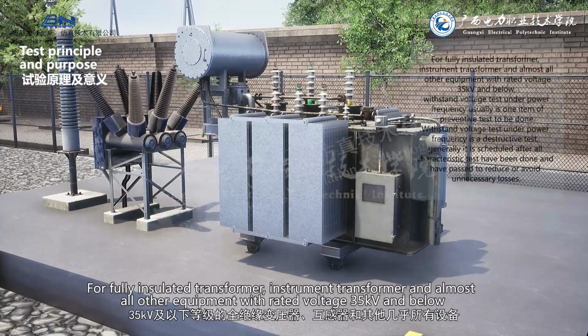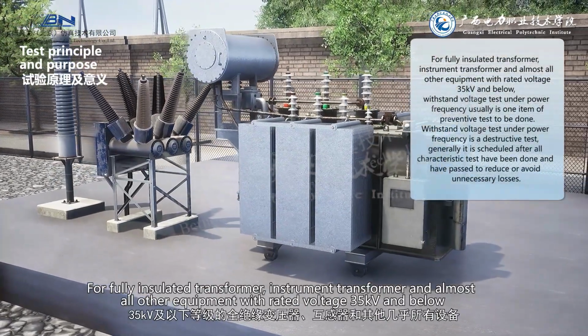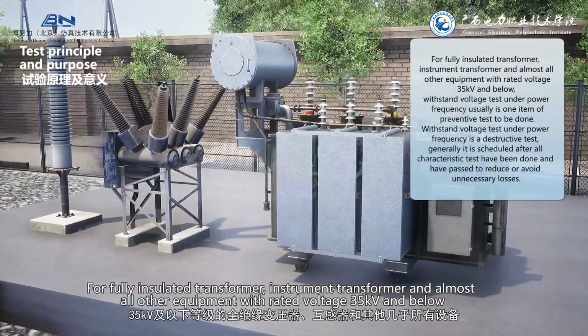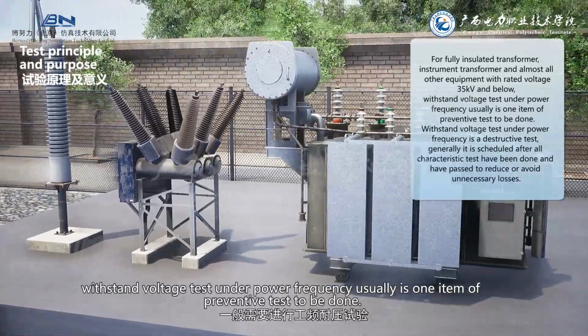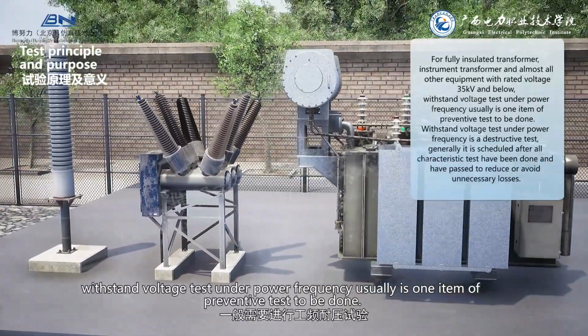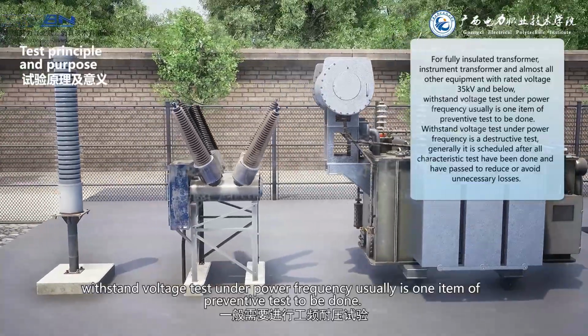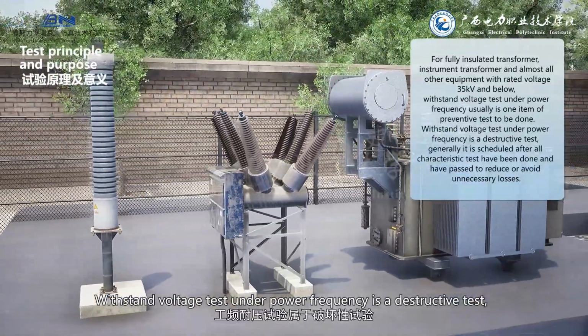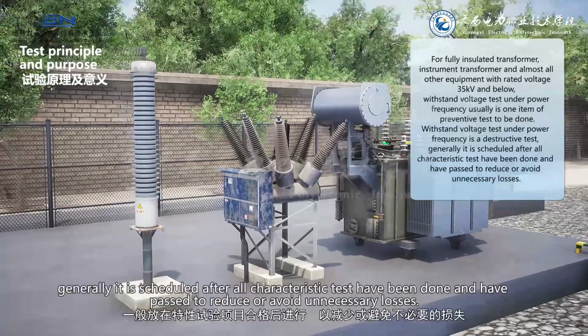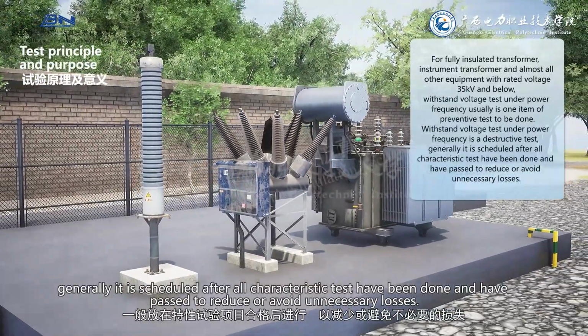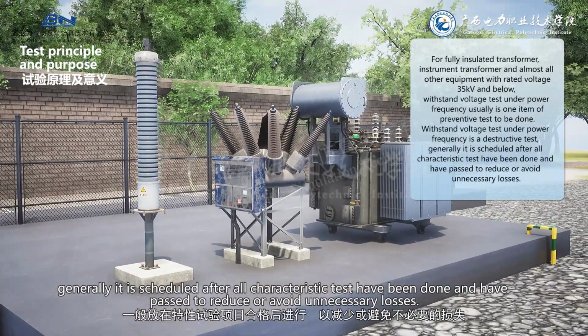For fully insulated transformers, instrument transformers, and almost all other equipment with rated voltage 35 kV and below, withstand voltage test under power frequency is usually one item of the preventive tests to be done. Withstand voltage test under power frequency is a destructive test. Generally it is scheduled after all characteristic tests have been done and passed, to reduce or avoid unnecessary losses.